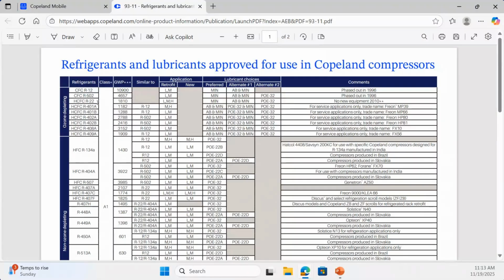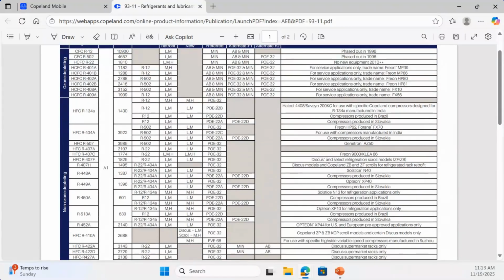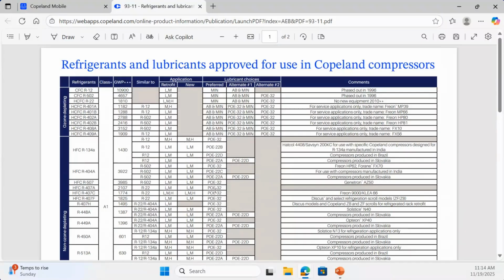Back in the day when we were using chlorine in refrigerants, we used mineral oil. As we started removing the chlorine, we went to alkyl benzene, and finally to POE, which, if you notice on this form, is actually backward compatible with a lot of the different refrigerants used out there now.